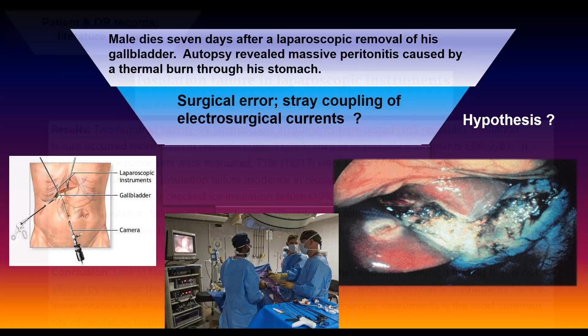He had actually gone back to the ED because he was claiming stomach pain. Ultimately, they found out that these laparoscopic instruments are typically cold sterilized with glutaraldehyde, and repeated cold sterilization has been shown to degrade the insulation. So it was either capacitive coupling or insulation breakdown that caused stray ESU currents, which burned a hole right through his stomach. He died of massive peritonitis as a result.